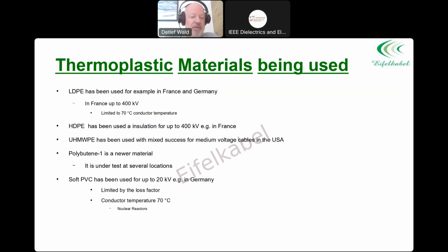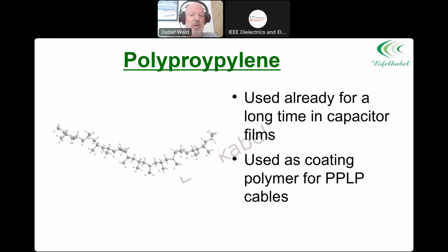Also for medium voltage, soft PVC has been used for up to 20 kV, for example in Germany, and those cables are still in their network. The limitation for higher voltages is the loss factor, and also the conductor temperature of 70 degrees. In nuclear reactors, it's used as a cross-linked FR version, according to my knowledge, but I won't go too far into this -- just to give you some background on other thermoplastic materials.